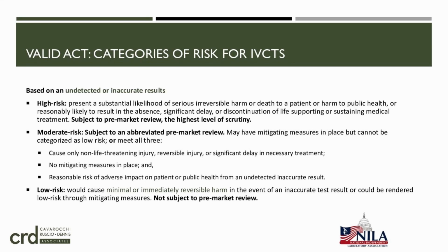Tests that are considered moderate risk. So this is actually a recently added category. This wasn't part of the original bill, but one of the last versions that we saw in the last couple of weeks added this classification for moderate risk. And it's a little bit complex, as you can see from the language on the slide, but tests that are classified as moderate risk would be subject to an abbreviated pre-market review. So still going through pre-market review, but less onerous than pre-market review for high-risk tests.